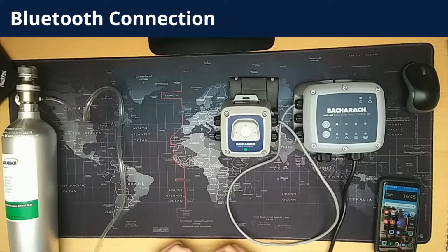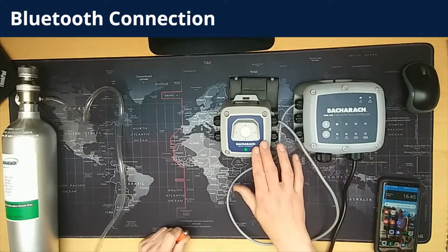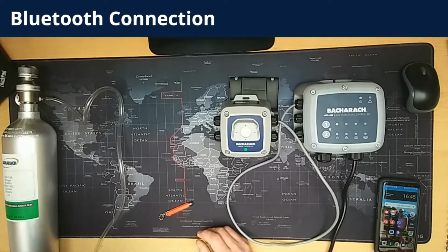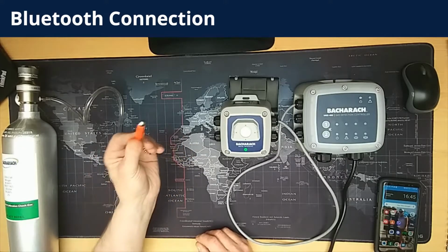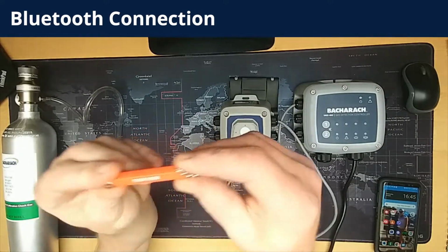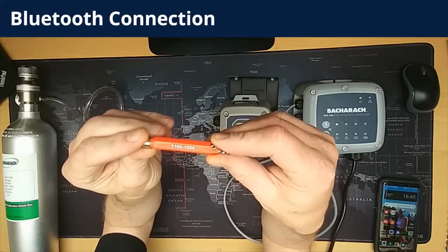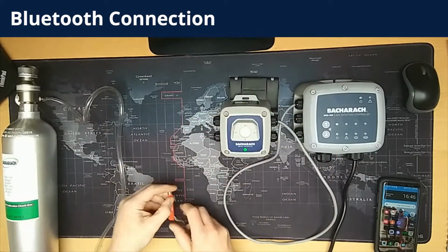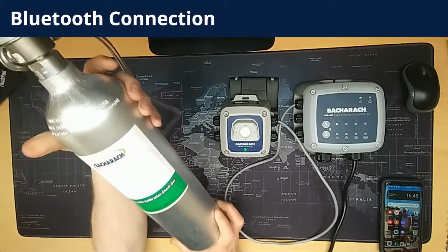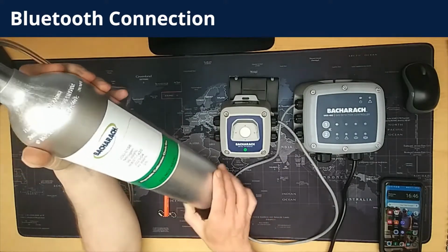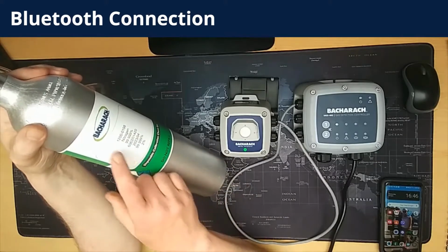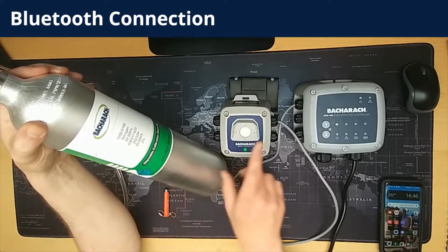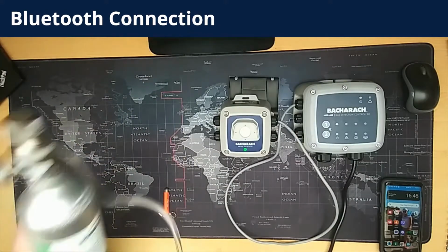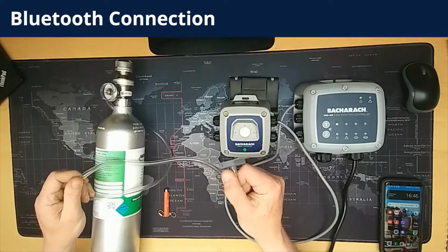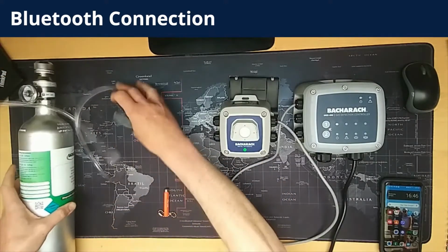So if we review the equipment we have, here we have a 402 and a 410. We also have the magnetic wand. That's the part number for the magnetic wand on the side. We have calibration gas. This cylinder is the zero gas. The details are on the front, and this cylinder is nitrogen, which we use for the CO2 detector that we're about to calibrate. The cylinder is fitted with the regulator, which is in the off position. We have the calibration tubing and the MGS-400 calibration adapter.